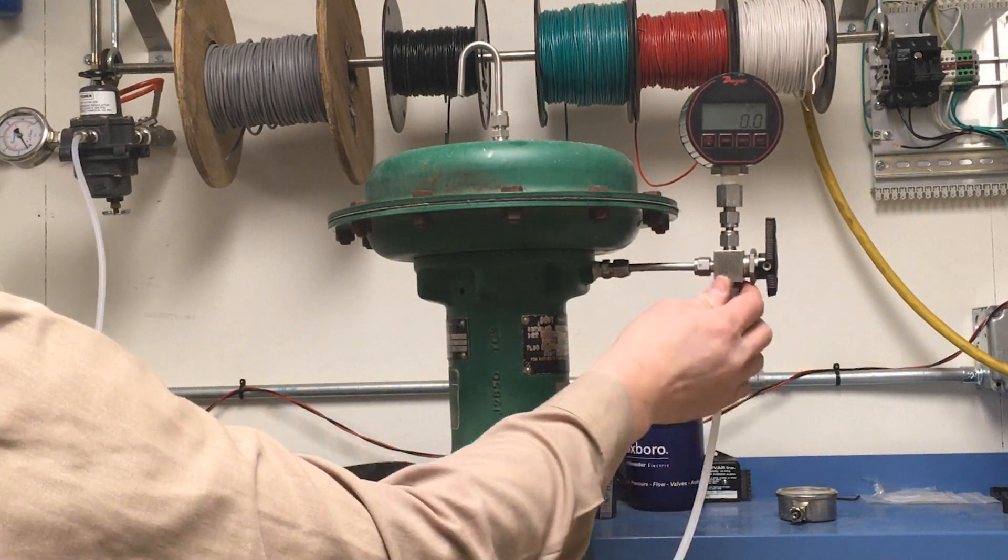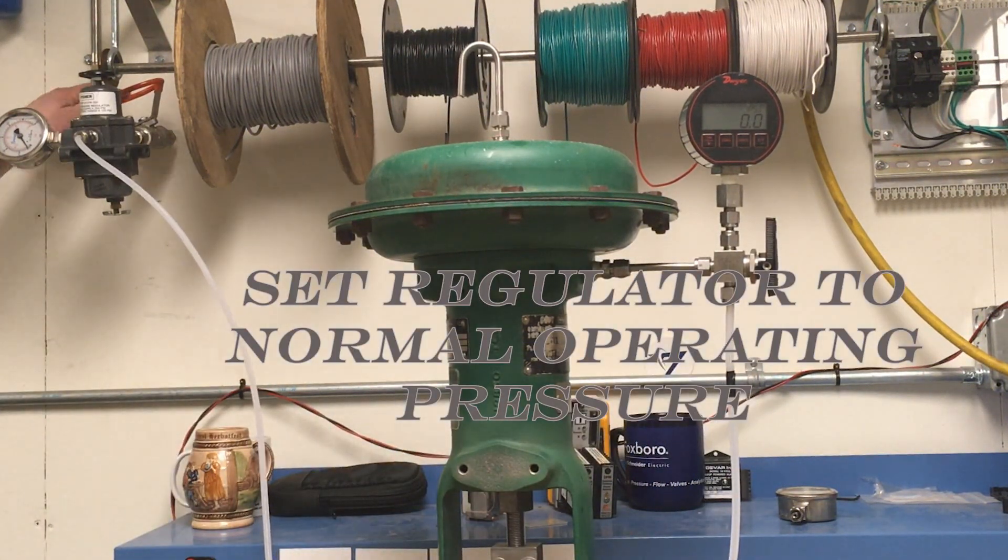The regulator should be adjusted to the normal operating pressure for the control valve. Once air is applied to the actuator, wait for the valve to reach its max travel position.